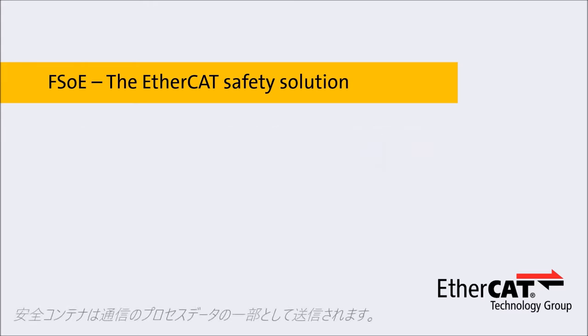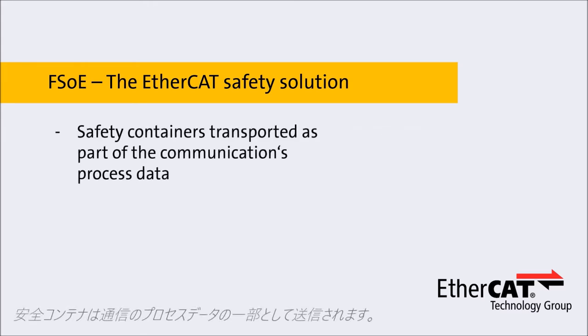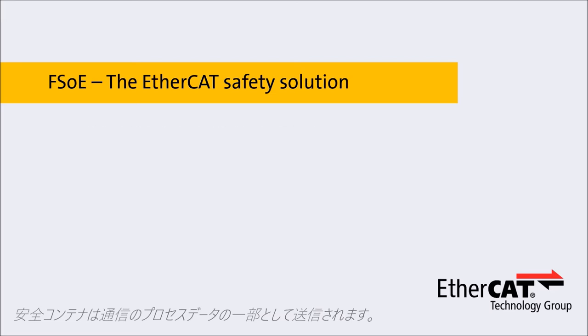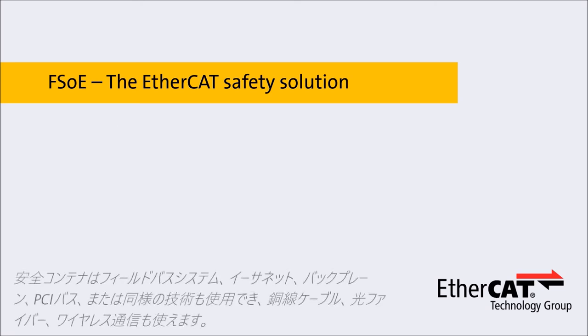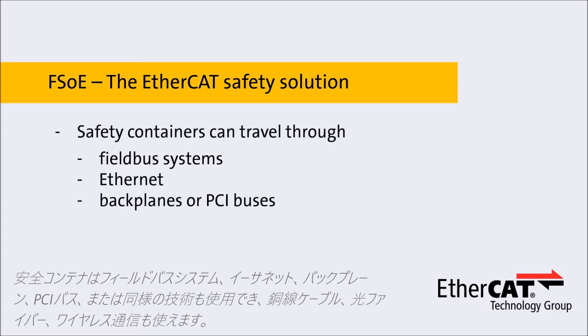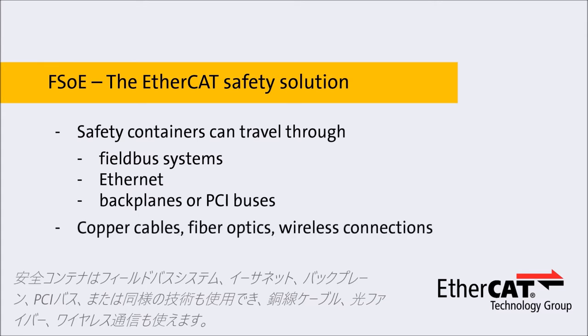The safety containers are transported as part of the communications process data. Whether data transfer is safe does not depend on the underlying communication technology and it isn't restricted to EtherCAT. Safety containers can travel through fieldbus systems, Ethernet, backplanes or PCI buses, and can make use of copper cables, fiber optics, and even wireless connections.